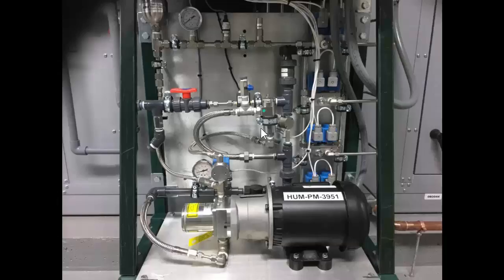One system may have more vibration than another, and that just has to do with the resonating effect of pulsation, meaning as you pulsate, it can actually be amplified through some of the piping just by the vibration of the piping itself. It can kind of amplify itself as it's vibrating, depending on how the piping is anchored down. And it can change its vibration due to the frequency of this particular pump. So as the pump starts to pump faster, the pulsation is a little bit faster, and you can feel it in the piping. So what may happen is, out within the piping in the building, there can become some different resonating pulses that can make it vibrate more or less.